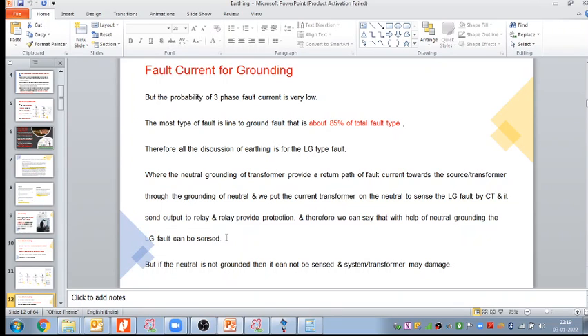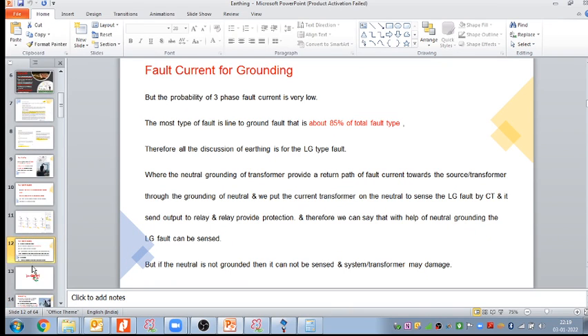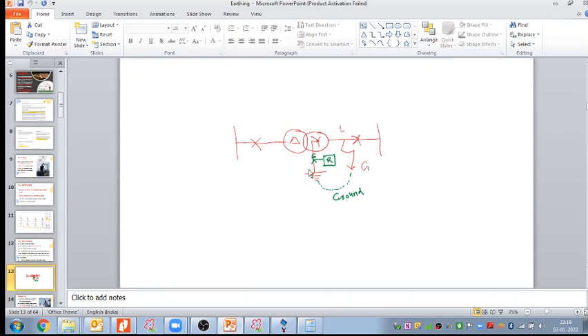But if the neutral is not grounded, then the fault cannot be sensed, and the system or transformer may be damaged. So this is the point. Here I have taken one example: in a delta star, a line to ground fault happens. This is the return path flowing back toward the transformer. Here we put the CT, and it gives output to the relay, and the relay will give a tripping command to this circuit breaker, and it will protect the transformer against damage.